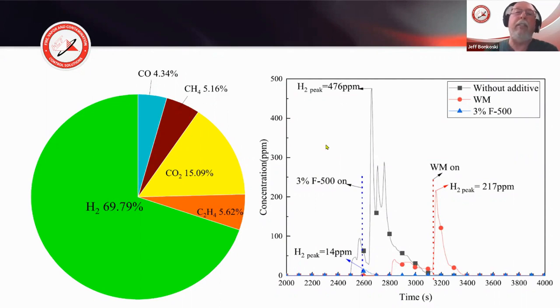Looking at this pie chart and the graph next to it, we see that the amount of hydrogen at its peak, without any additives, was 476 parts per million. With water mist, they were able to drop that hydrogen down to 217 parts per million. But when they added 3% of F500 into the water, they were able to drop the hydrogen down to 14 parts per million.